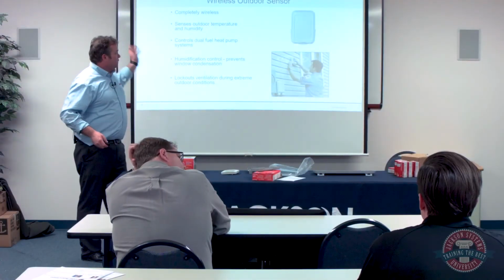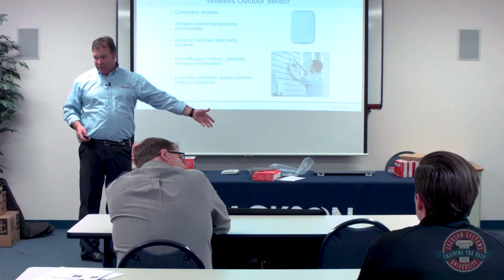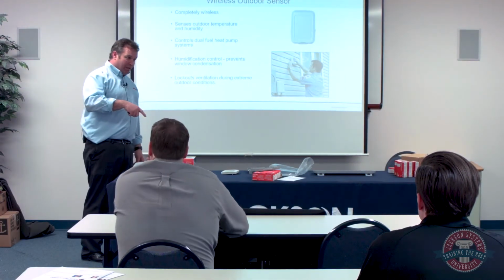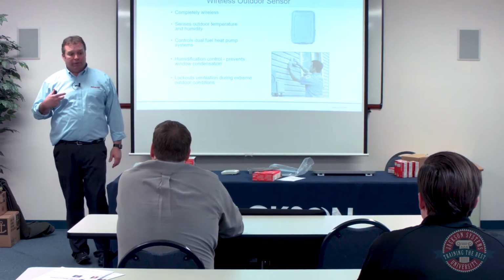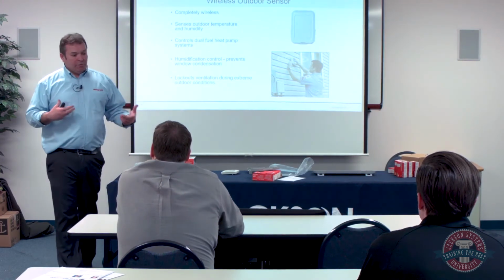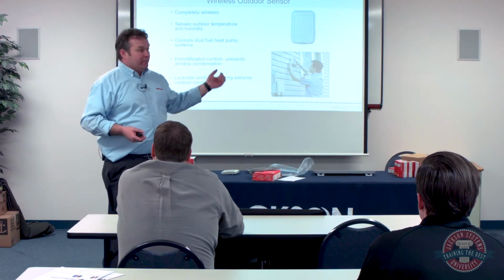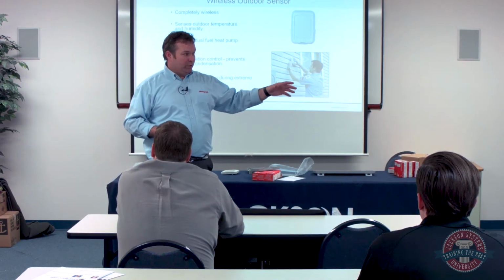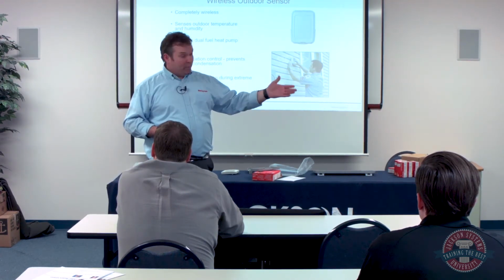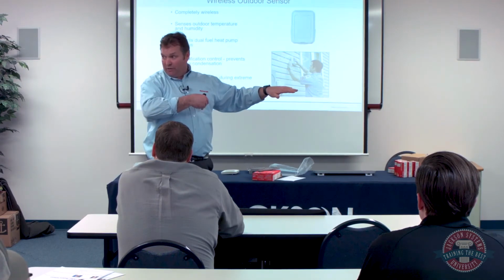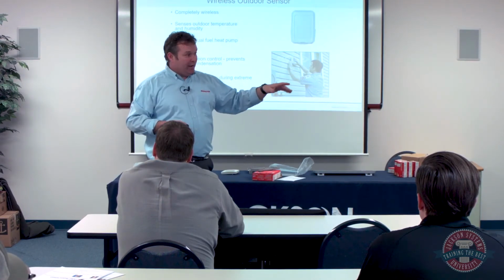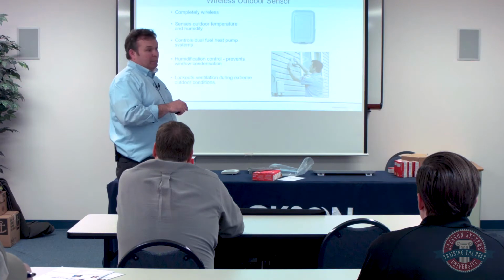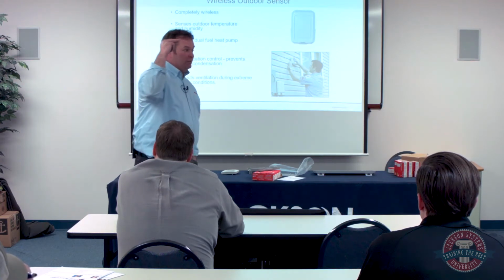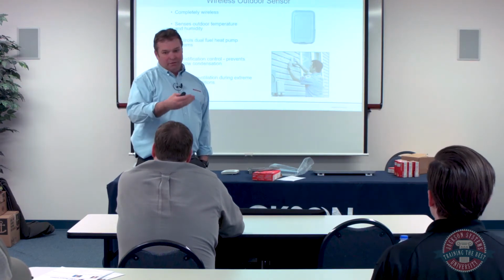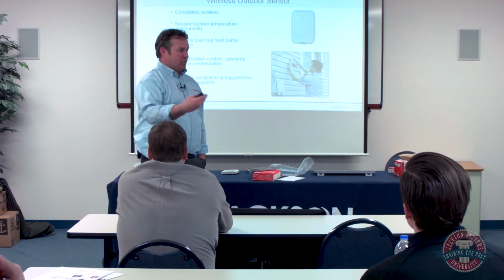The outdoor sensor, one sensor will power 16 RedLink thermostats. It reads temperature and humidity, and does more than just show you the outside temperature. If I have a ventilator, like a normally closed damper that opens to bring in fresh air, it'll modulate that. You can also set limits, like if it's 100 degrees outside, don't bring that air into the house, wait until it gets to a normal temperature.